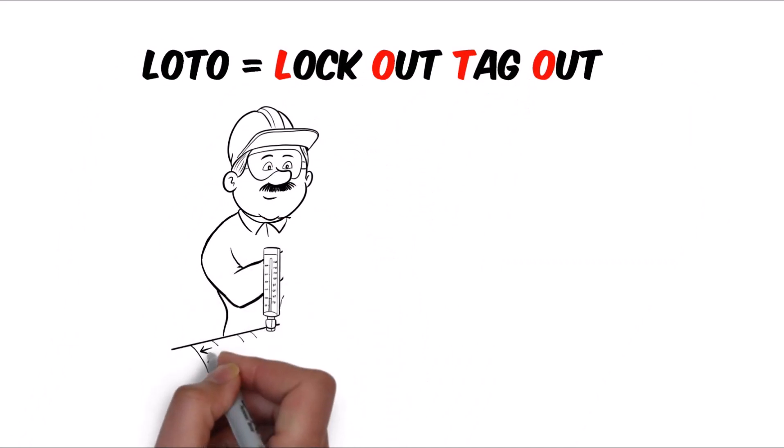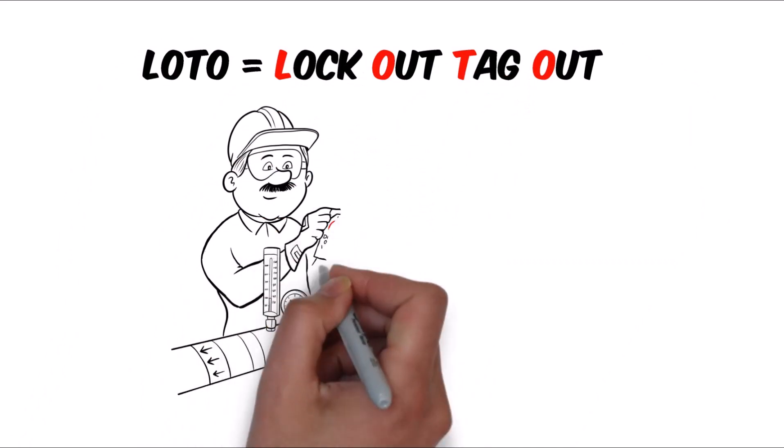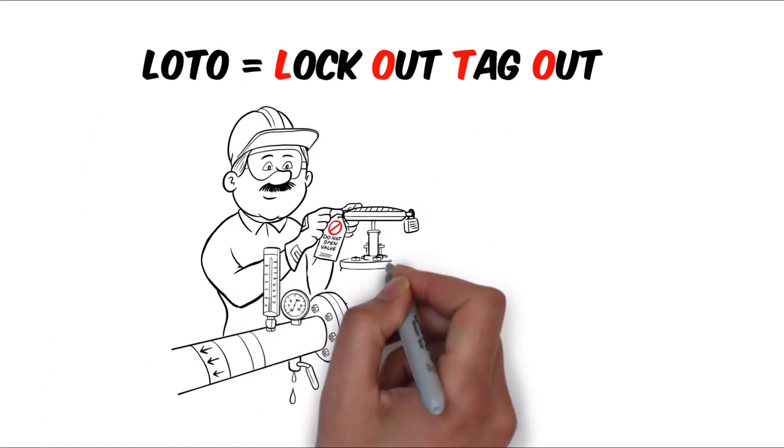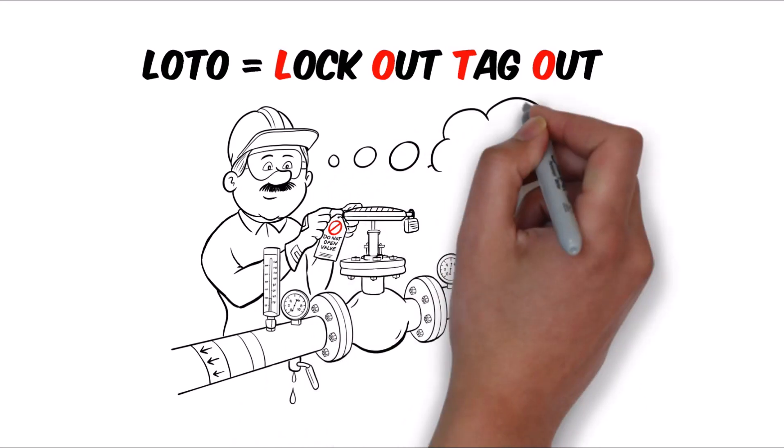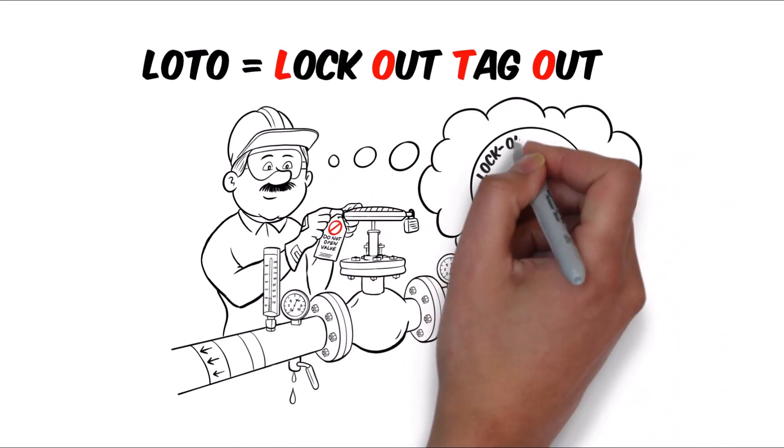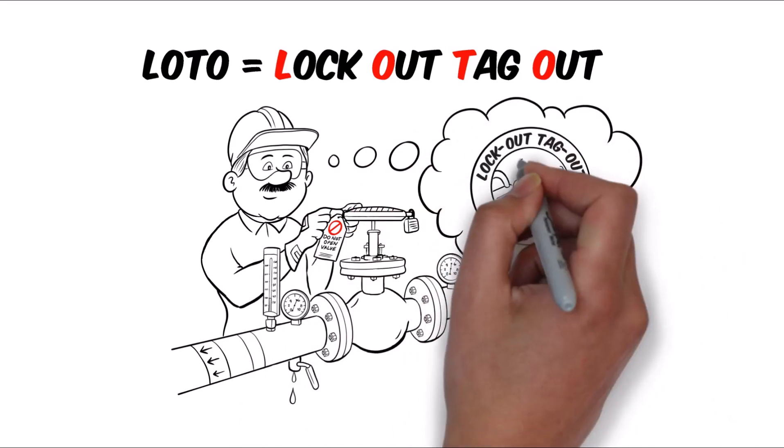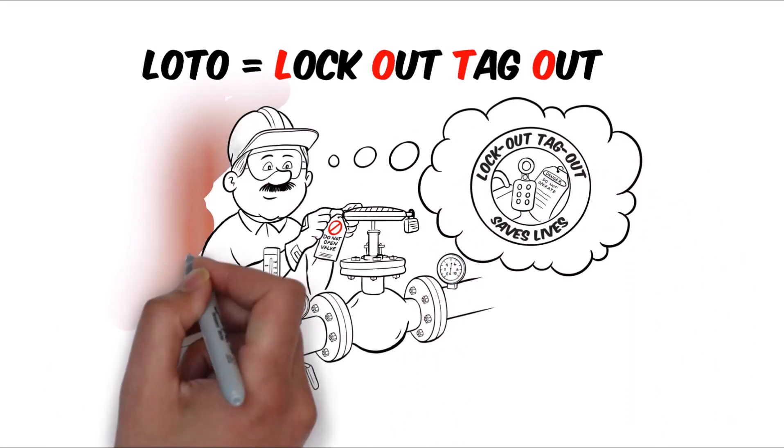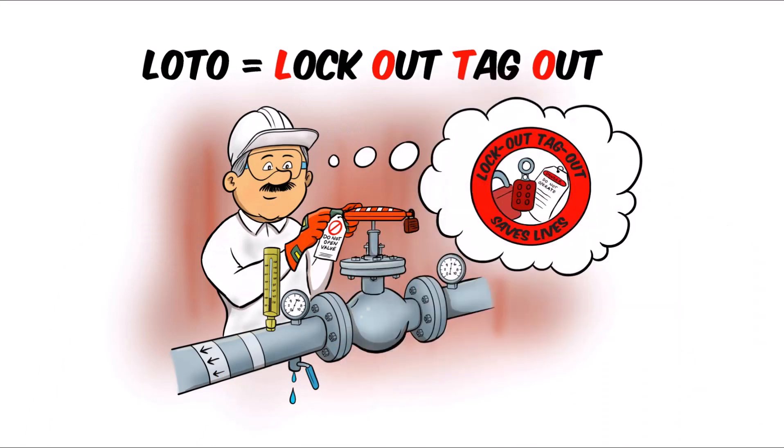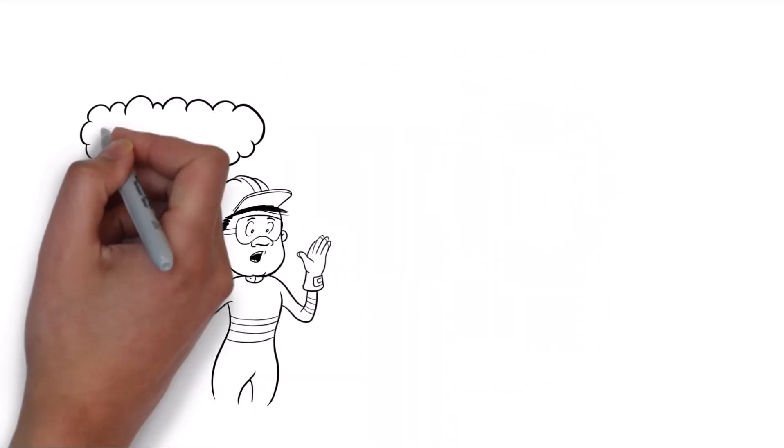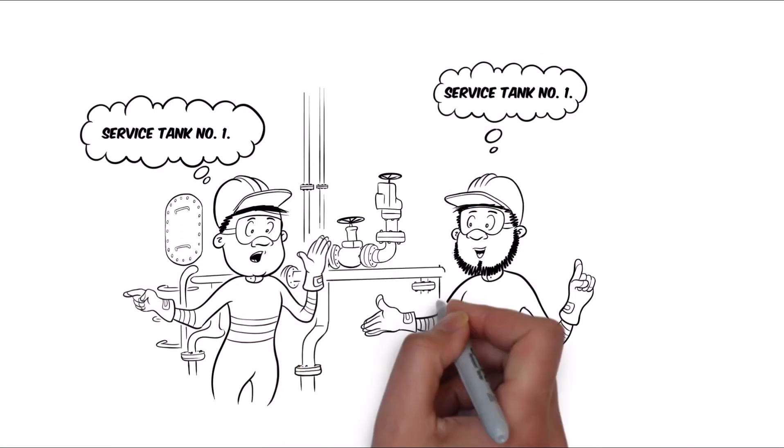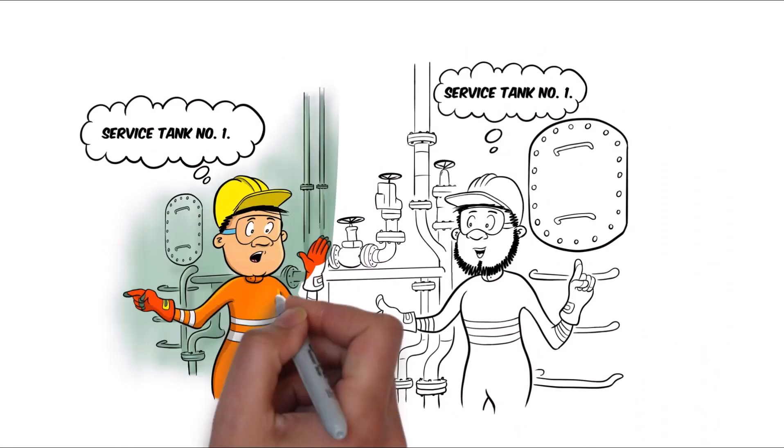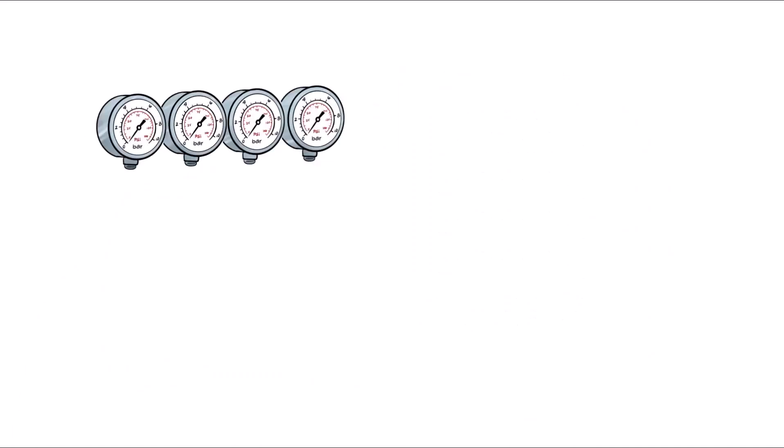Confirm that the system you are planning to work on is isolated and prevented from use. Secure relevant valves with locks and tag them. Display warning notices in key places. The use of LOTO is particularly important if the preparation work is carried out by a third person. If a tank manhole is to be opened, ensure that it leads to a desired compartment.